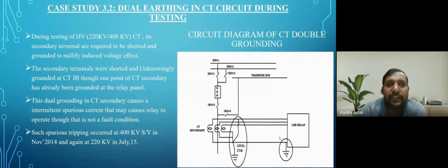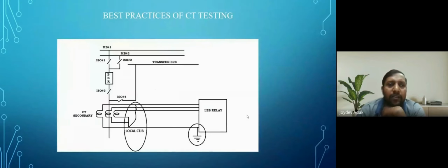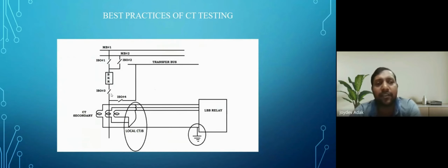So this occurs due to dual earthing in the CT secondary circuit during testing. Then what have we done? We have adopted the best practice of not grounding at this end, only shorting. So only one single ground will not hamper any system. This is the practice we have adopted from this type of tripping.